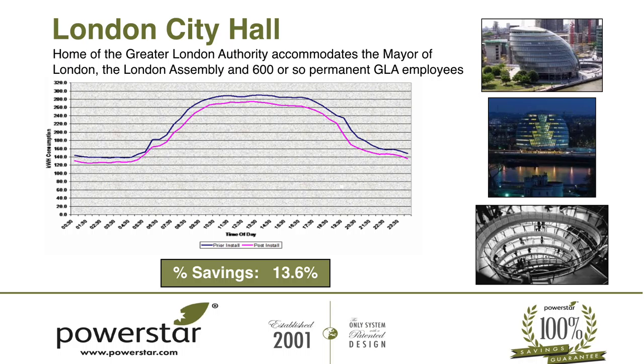London City Hall achieved a 13.6% energy saving, again verified by IPMVP. They have 500 kilowatts of solar PV — their solar PV output improved by 10% after voltage optimisation went in, because the inverters were now running at the correct voltage output within the correct inverter curve. So voltage optimisation and solar do go hand in hand.